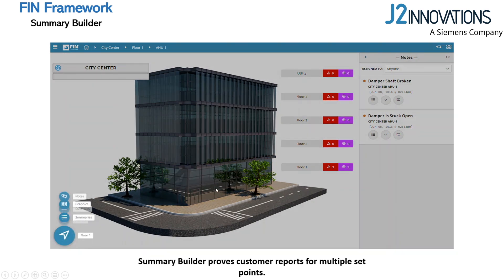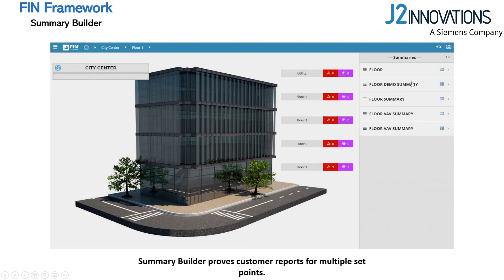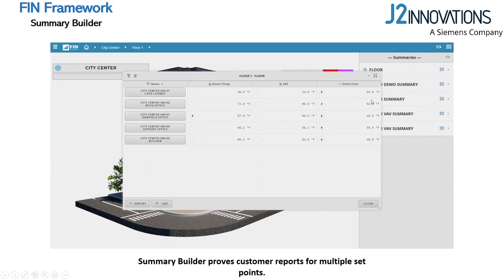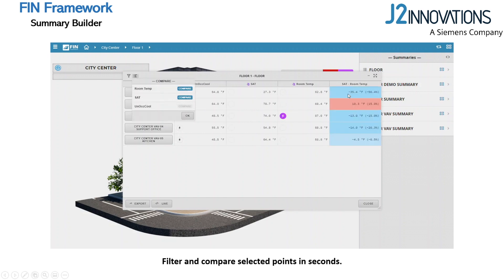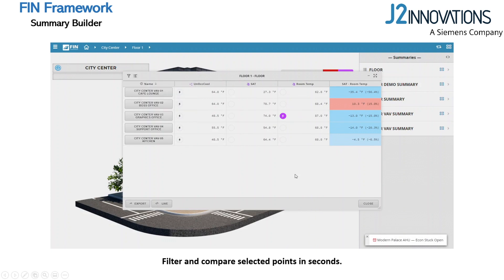Returning to Floor 1 and selecting Summaries, you'll see the summary we just created. From here, we can access the graphic or any of the tools associated with that device. We can also manually command points to set specific modes, see which points are in override, add comparisons, and export data points to either a CSV or a PDF to share and document data.